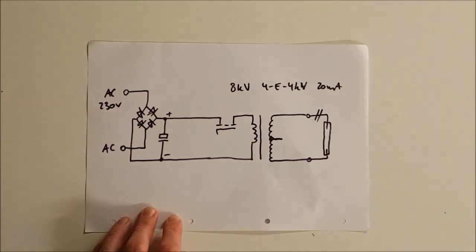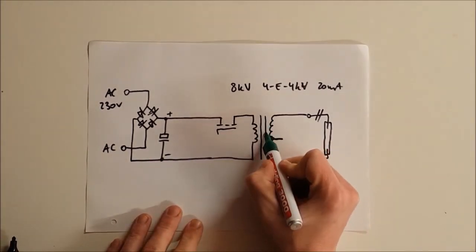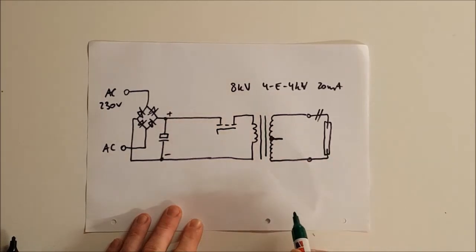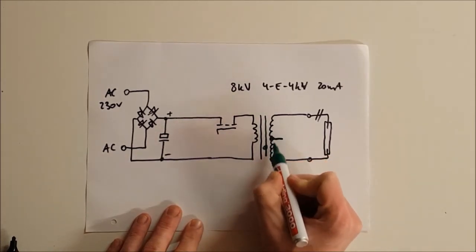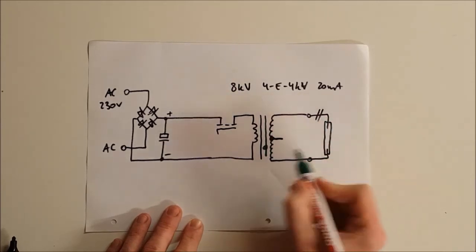And that can be detected electronically. For example, some transformers detect it with an antenna that is glued to the case of the output winding, so they have a piece of copper glued here or something. And this antenna can be used to measure the electric field that goes up in open secondary condition.